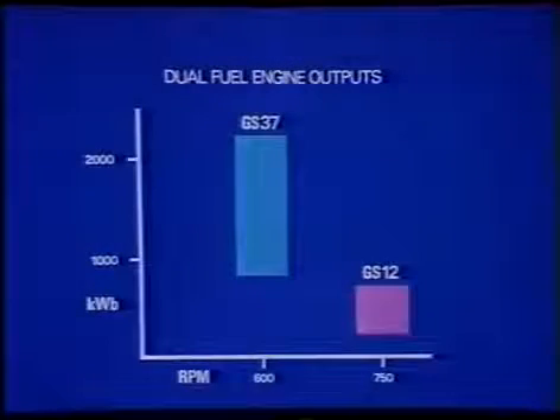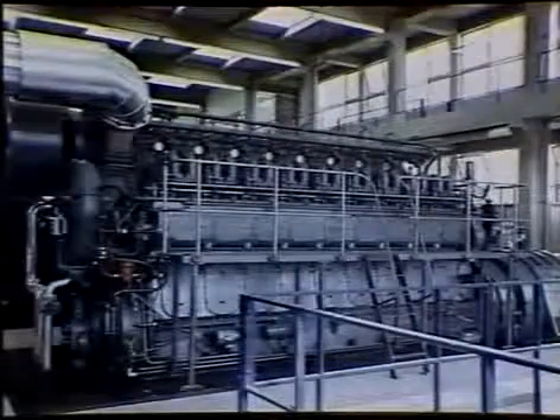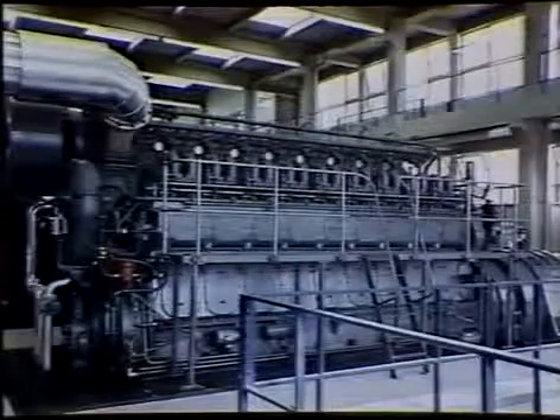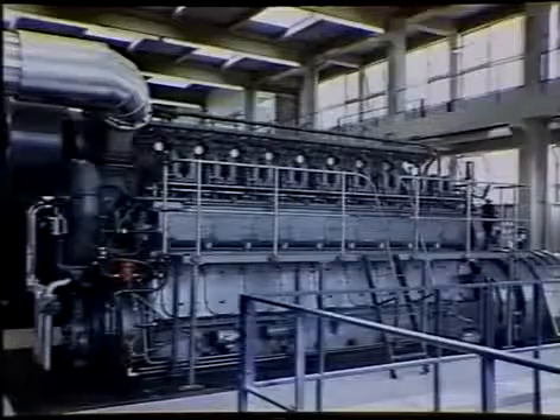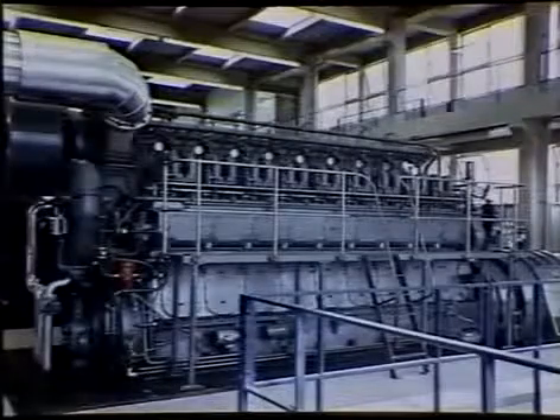Both GS12 and GS37 type engines are available for dual fuel operation. In this mode, diesel fuel is used for ignition purposes only, the main fuel input being either natural gas or sewage gas. Engines can be offered for outputs of up to 2.5 megawatts, and have the ability to revert automatically to diesel operation in the event of gas supply failure.